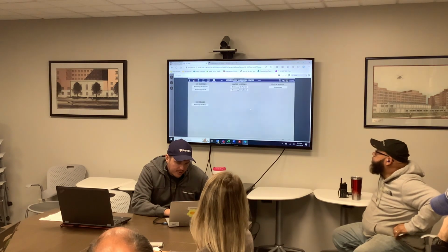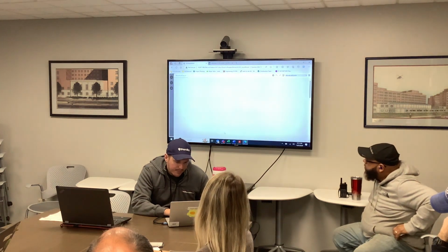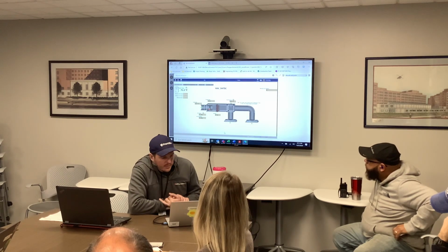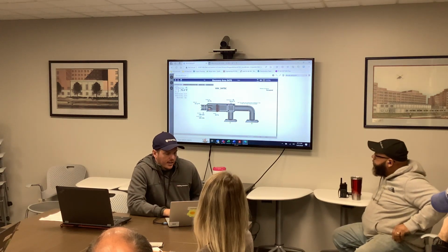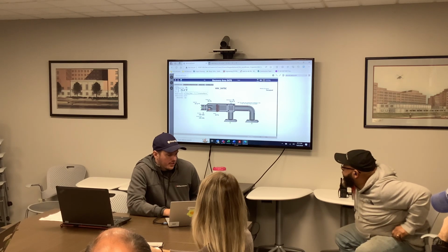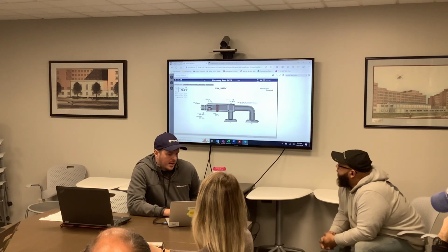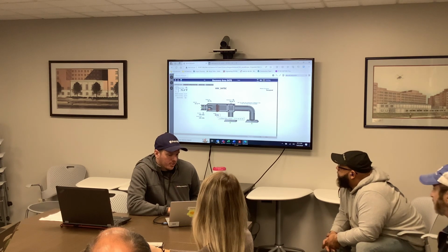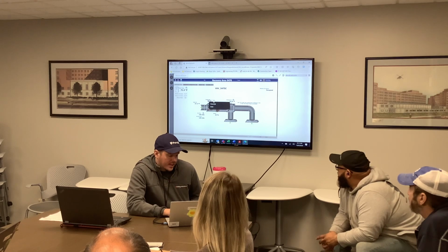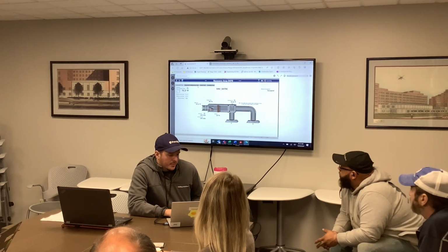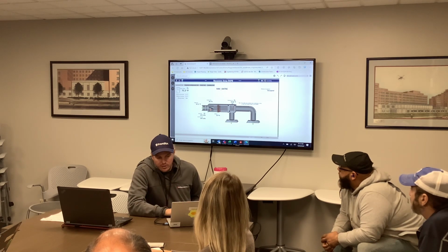Okay, I'm gonna go back to the 5th floor, back to endoscopy, and let's choose a VAV. Give it a moment to boot up. Just like every other VAV I'm sure you're used to, you can see your zone temp, your effective heating and cooling set points, your damper position, your airflow, and what your reheat is doing. This one is overrideable, so it's a damper. You can see your supply air coming in from the unit, 57, you can see your coil open, and you can see your discharge, so you know your coil is working.